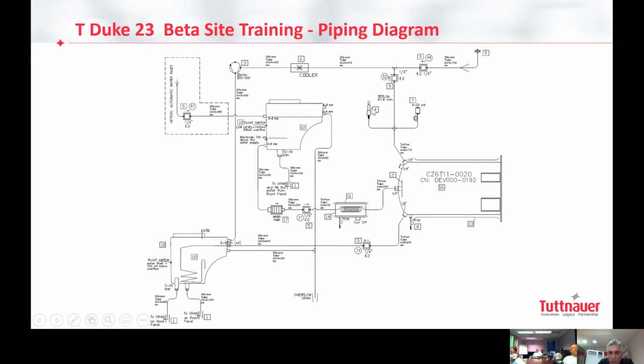We also have the safety valve to protect. Once the vacuum pump starts running, from here this valve gets open, the chiller starts running to cool down, and the vacuum pump goes straight into the waste tank. Pressure goes down and down to the point we set. We set 20 kPa, which means 24 inch or whatever it is. Done. It reached, the pump stops, the chiller stops. I'm not sure the pump is stopped; maybe it will keep running, but this is the concept. Forget it, it's not so relevant for now. There are two ways of thinking, but it is out of scope for this point.